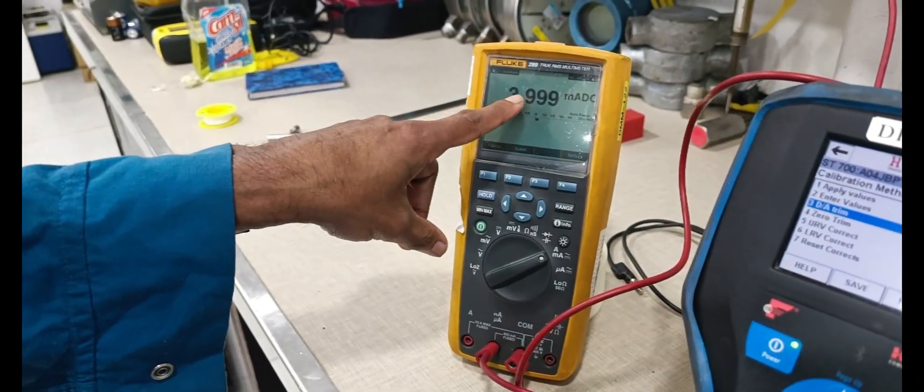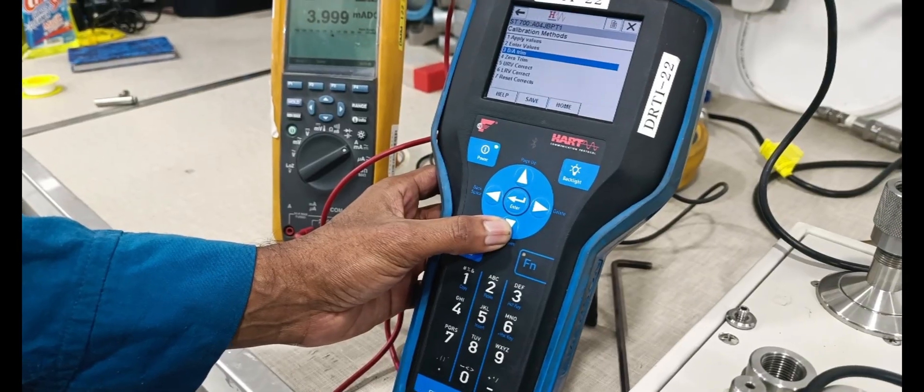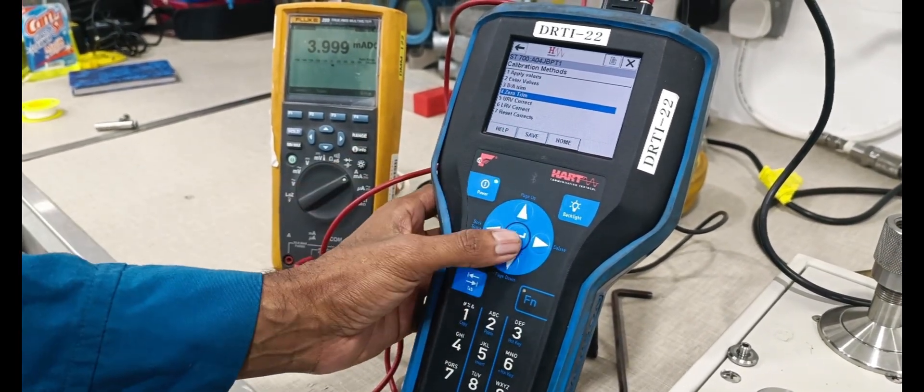Now mA is 3.999 milliamps. Next, we are doing the zero trimming selection — zero trim, enter.